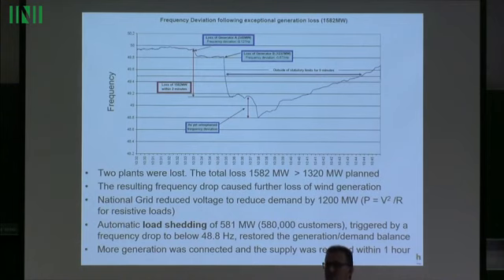That's why I'm saying it's the wind power. When there were just very few wind turbines, they had under-frequency protection and what's called rate of change of frequency, the derivative of frequency, as a protection. Those wind turbines are somewhere down the distribution networks, and the typical reason for a blackout isn't something dramatic, it's a digger cutting through a cable. The villages suddenly lose power - this accounts for 90% of power loss, these kinds of things.